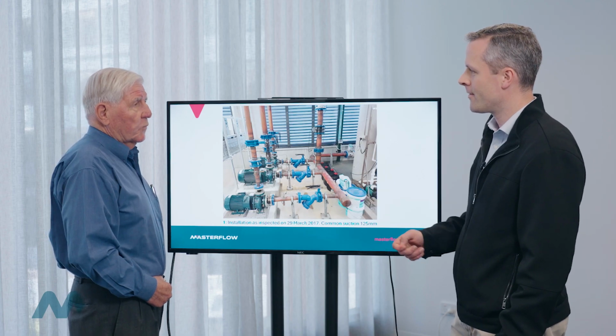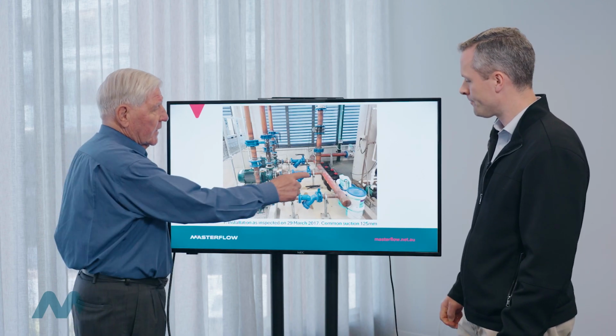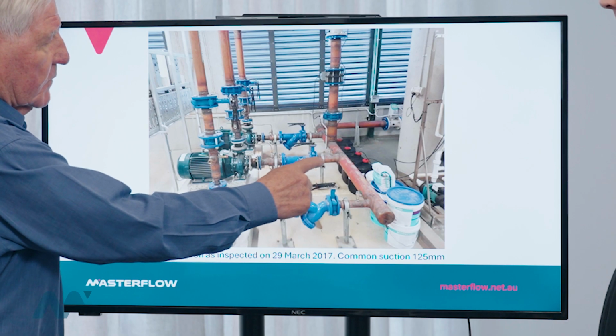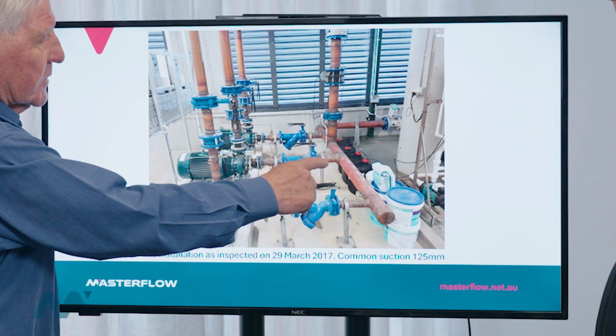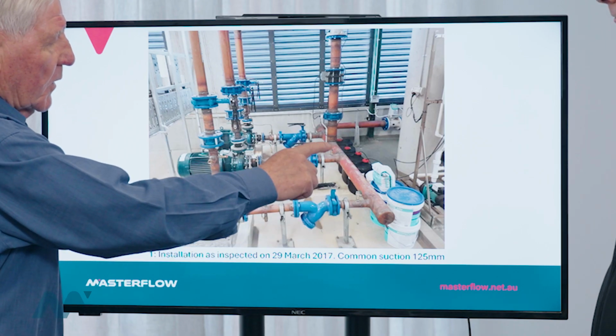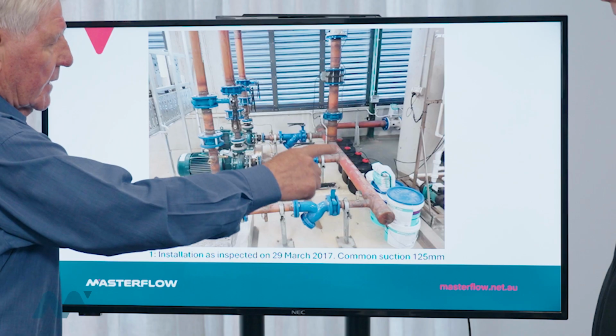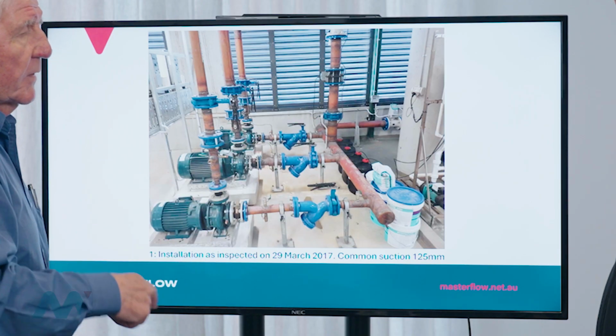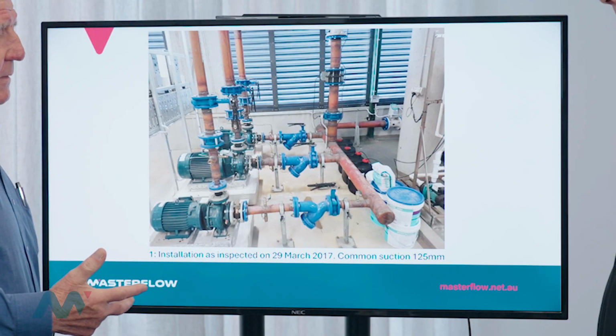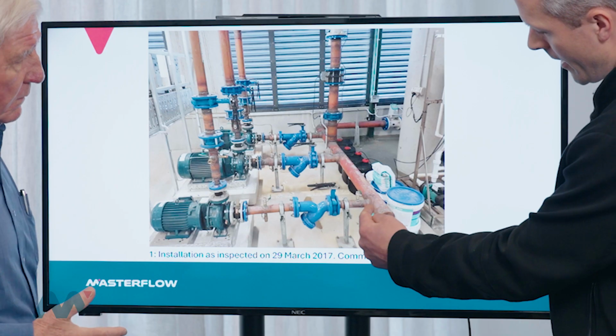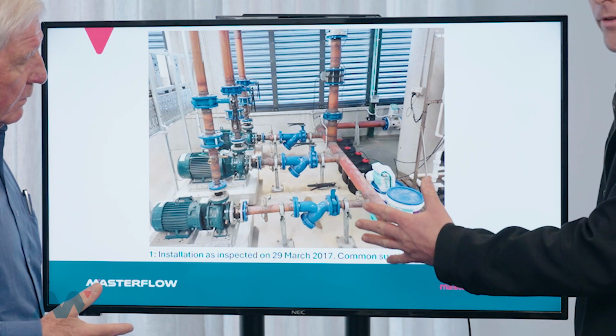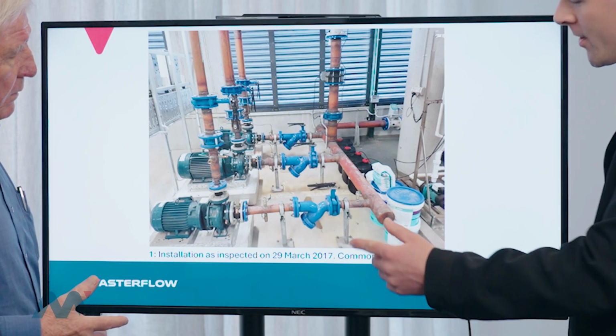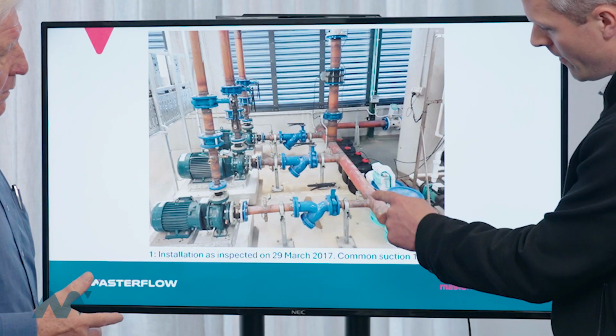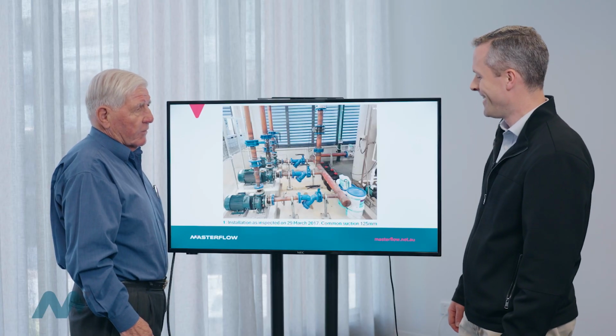No, it's a question of where the trap is. I mean, at the end of the day, the centre line of this small pipe is on the centre line of the bigger pipe, which means that there's a vacant area above that could have air trapped in it. I'm just noticing too, we have a dead leg here. I know it's often done in the industry, but best practice is this should have been an elbow. Don't think it makes a lot of difference, to be honest with you.